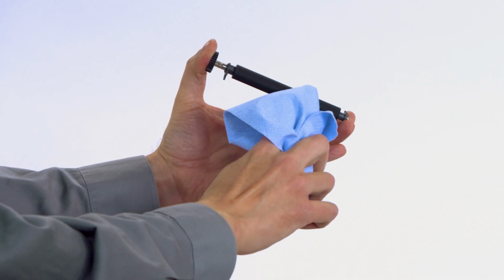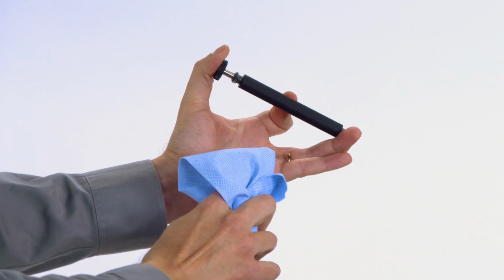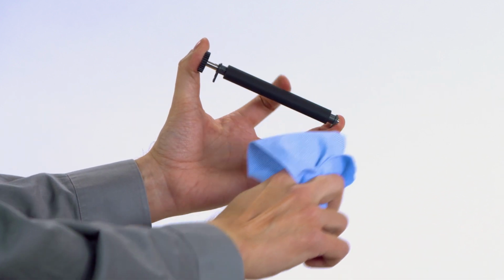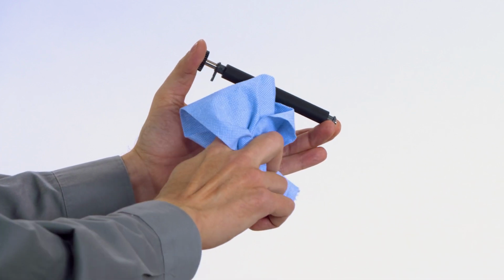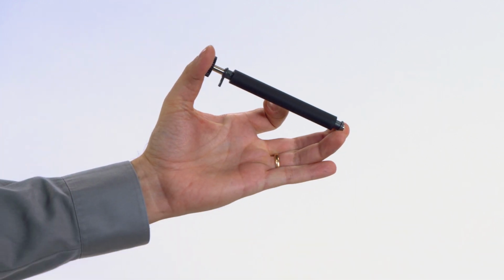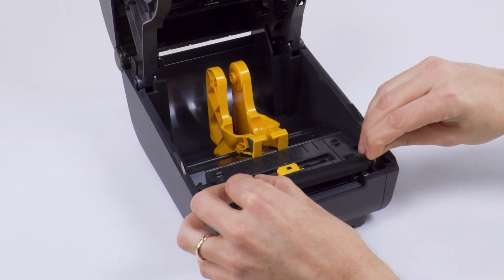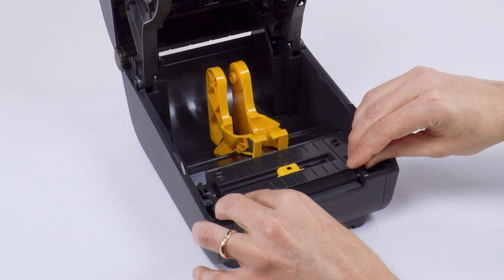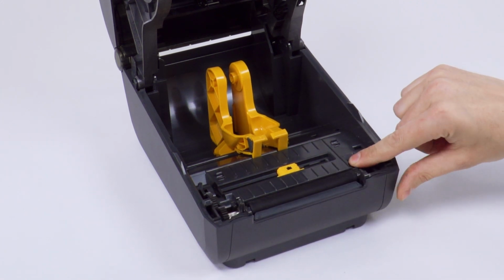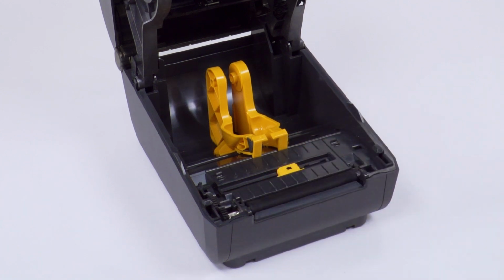Isopropyl alcohol can thin adhesives and oils without completely removing the debris. Clean the platen roller while turning and moving from end to end. If there has been a label jam or adhesive buildup, repeat the cleaning with a new cloth or swab until all leftover adhesive and debris are removed. Gently rub and blot the debris away with the isopropyl alcohol. Do not scrub the platen. Scrubbing can damage the platen surface. Allow the platen to completely dry. Lower the platen roller assembly into the bottom frame of the printer. Rotate each retainer down until it locks. Close the printer.